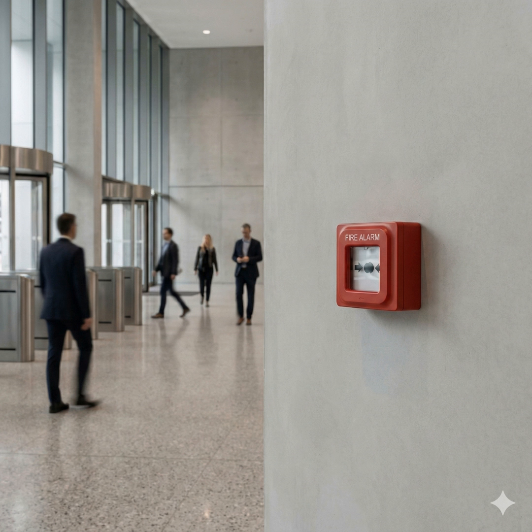The moment an alarm is confirmed, we are talking about integrated building systems coming online automatically. This includes coordinating things like HVAC shutdown to stop smoke from spreading through the ventilation, and the crucial elevator recall sequence, sending cars to a safe floor so emergency responders can actually use them. And that functional integration is the key takeaway right from the start. Physical safety is now inextricably linked to building intelligence.